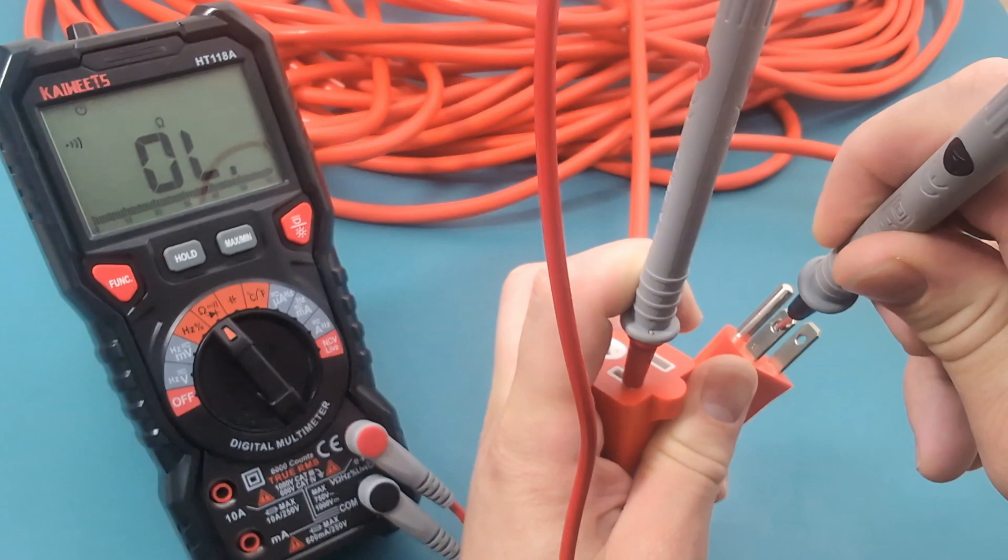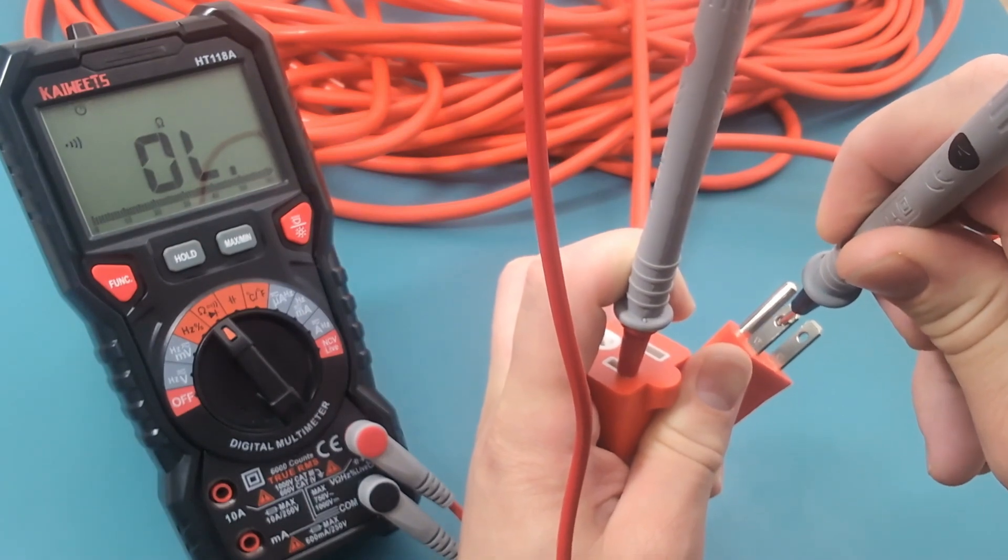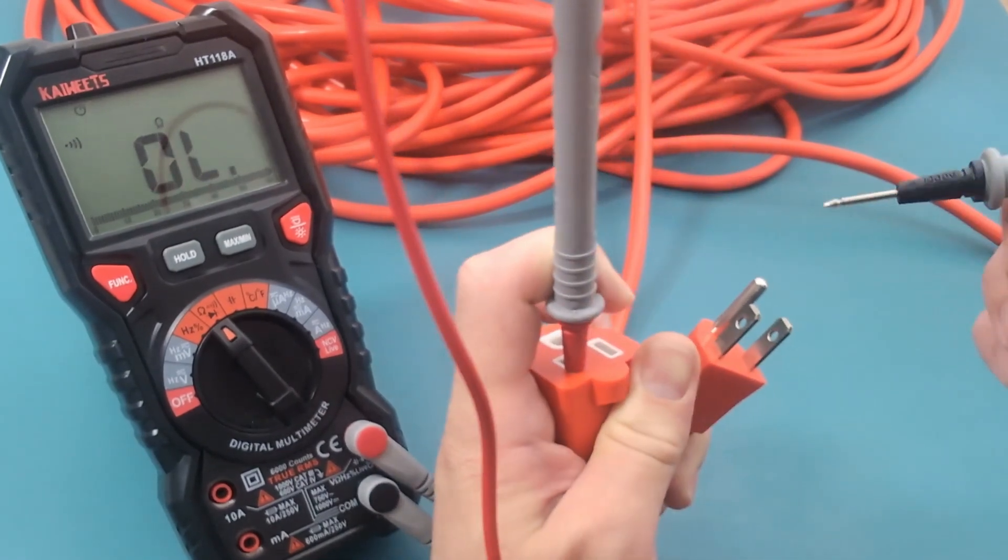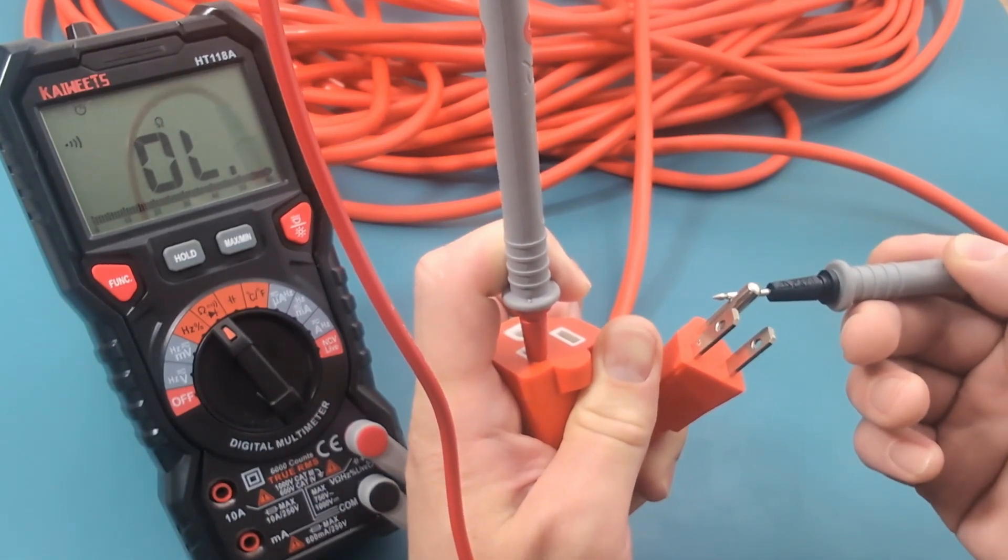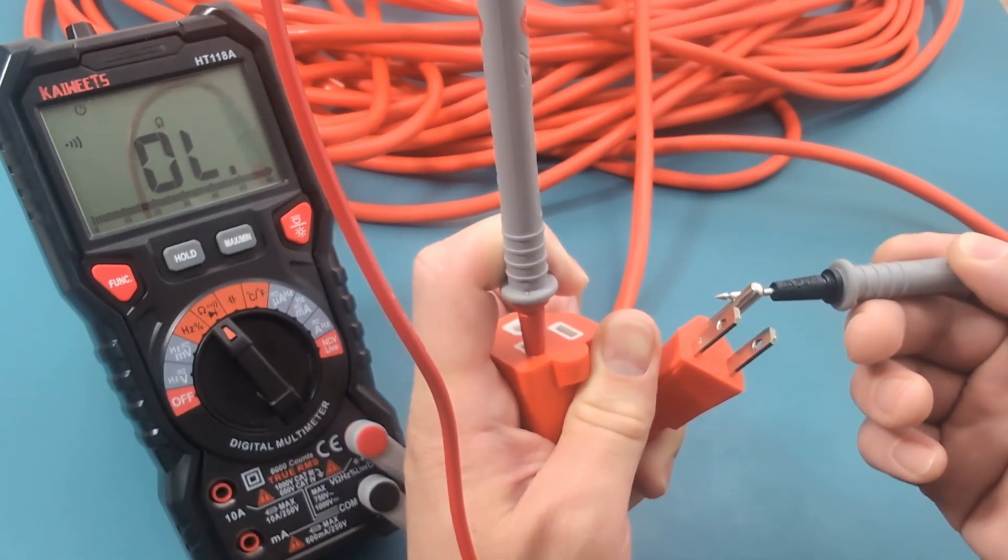Touch the other probe to the neutral and ground terminals. There should be no continuity or resistance. Since there is no continuity, we have verified that there are no short circuits. The hot terminals are good.